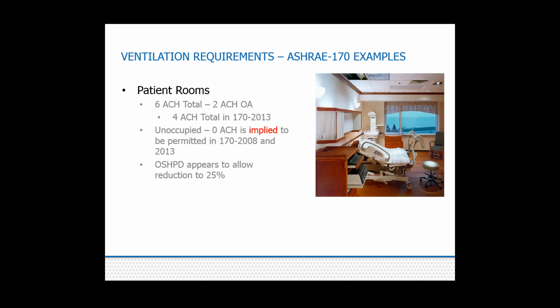Also, I think the wording could be a little more clear, but my reading of the wording in Standard 170 is that an unoccupied patient room has no requirement for air changes. The actual wording says that pressurized spaces can be set back to the minimum required to maintain the required pressure relationship, and it doesn't quite mention spaces that don't have a pressure relationship, but I think it's pretty well implied that it means there isn't a requirement.